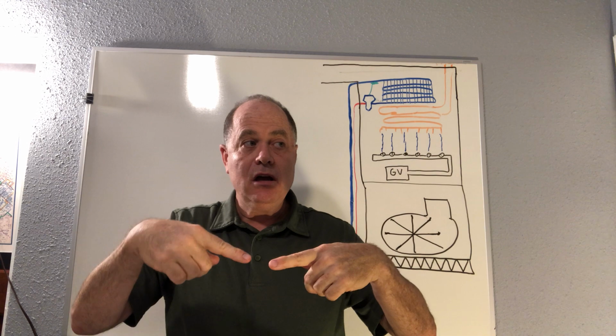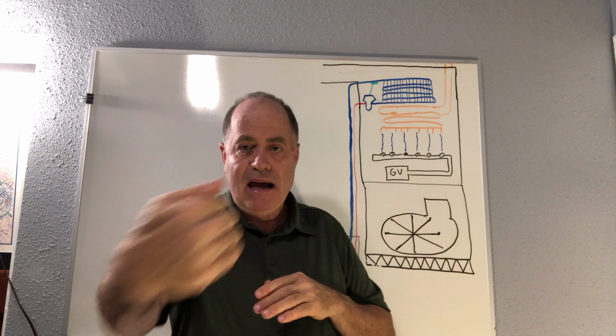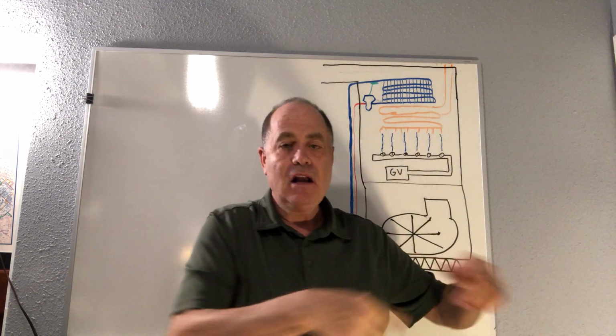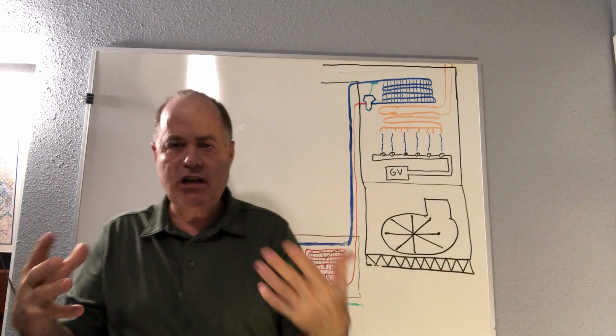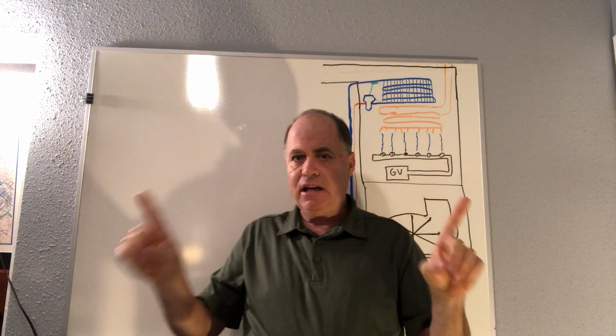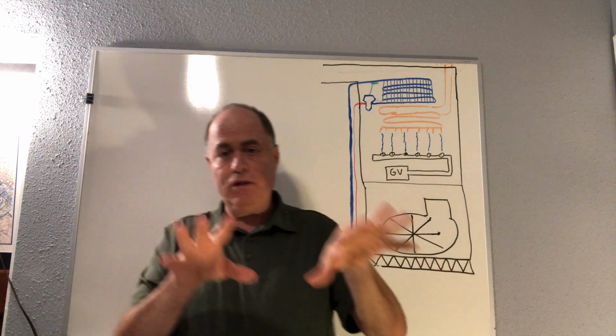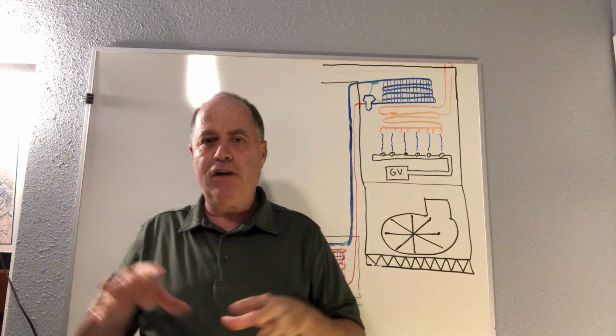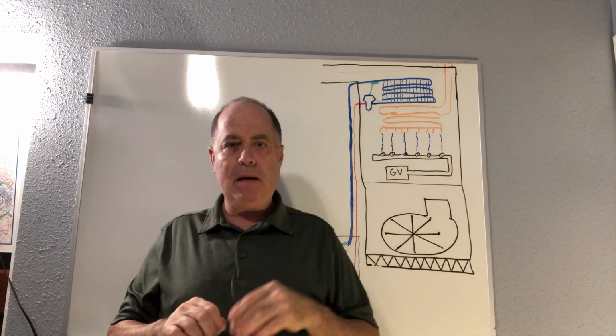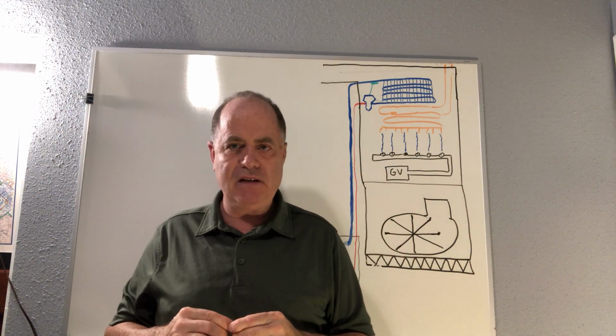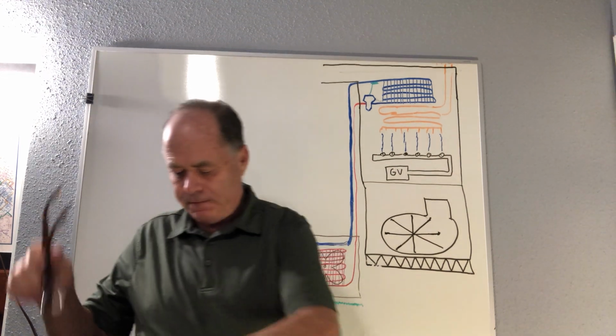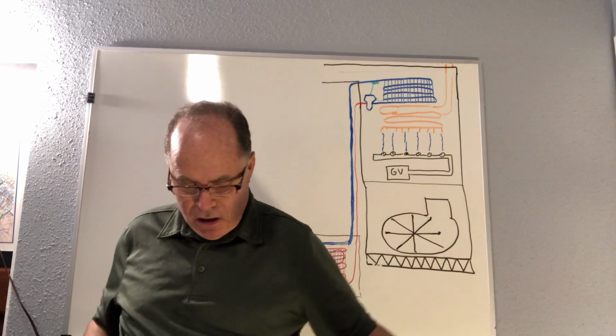The one serving inside your house has to make an air change like this, and it's a centrifugal fan, right? Like a squirrel cage fan. So you can't be attaching ductwork to a unit like a unit heater that's designed with a prop fan and then messing up the airflow and everything by putting ductwork on, and that prop fan is not designed for that. Okay. All right.